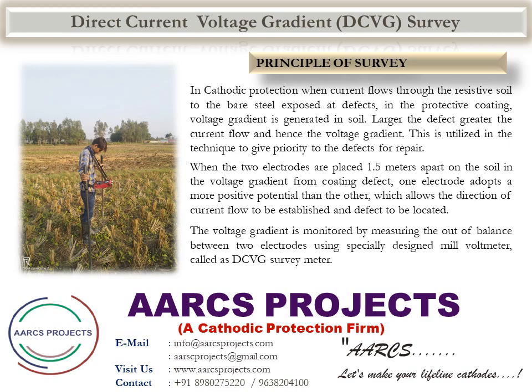This is utilized in the technique to give priority to defects for repair. When the two electrodes are placed approximately one and a half meters apart on the soil and a voltage gradient from a coating defect is present, one electrode adopts a more positive potential than the other, which allows the direction of current flow to be established and the defect to be located. The voltage gradient is monitored by measuring the out-of-balance between two electrodes using a specially designed millivolt meter, called the DCVG survey meter.